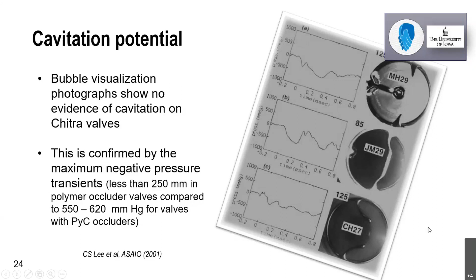Medtronic Hall is a pyrolytic carbon based valve. Here, simultaneously, they recorded the negative pressure ranges. You can see that in the case of the soft disk valve, the negative pressure doesn't go to very low levels, and thereby there is no chance for this cavitation formation. This is one of the major findings in this particular device. And in fact, this was one of the reasons why this particular device got good entry into artificial left ventricular assist devices, total artificial heart assemblies, etc., because of the ability to resist cavitation formation.